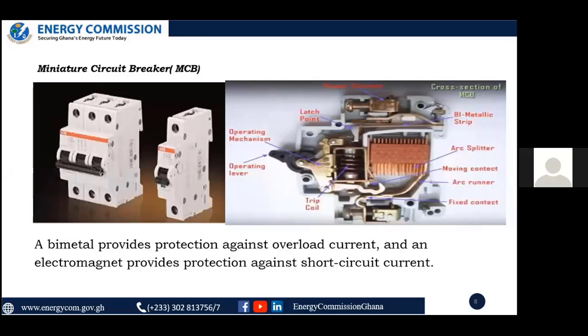So this is how the miniature circuit breaker works. It trips on two disturbances: when there's a short circuit and when there's an overload current. Overload current means the current in the circuit which this miniature circuit breaker, or MCB, is protecting has gone above the rated current. For example, we have a 6 amp miniature circuit breaker, and it is supposed to operate when the current surpasses 6 amps. So let's say a current of 7 amps or 8 amps flows through it for a certain period, let's say some milliseconds. Then this miniature circuit breaker would have to operate.